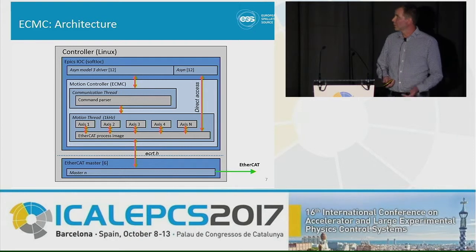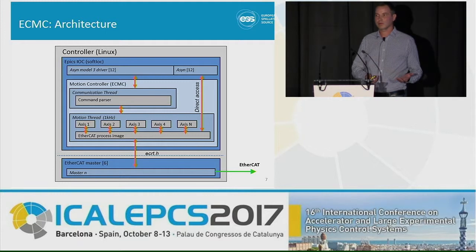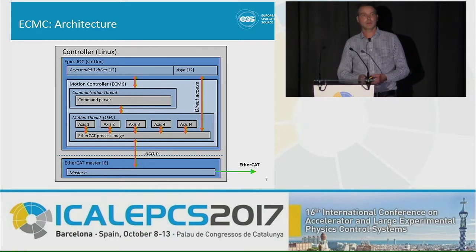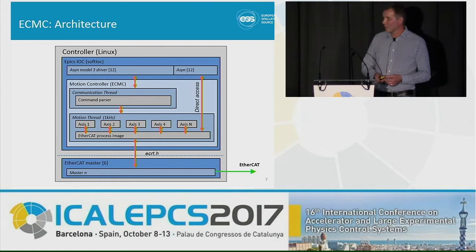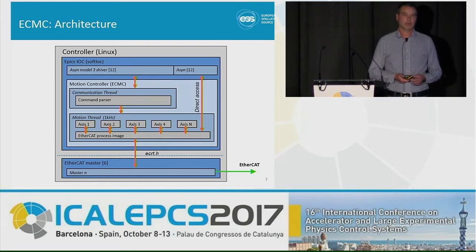This is an overview of the architecture of our system. It's integrated into the EPICS environment, and we have integrated an EEE module — an ESS EPICS Environment module. All communication to EPICS records is handled through the Asyn interface. The motor record communicates through something called the Model 3 motor driver. ECMC consists of two threads: one communication thread, which includes a command parser for configuration and slow communications.